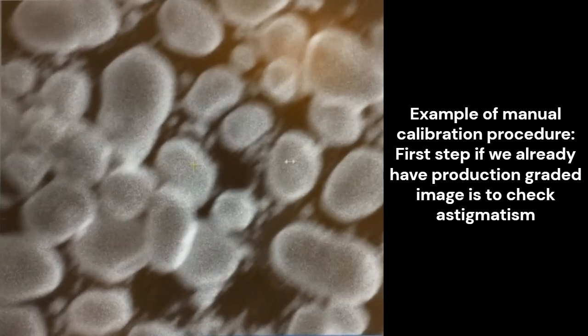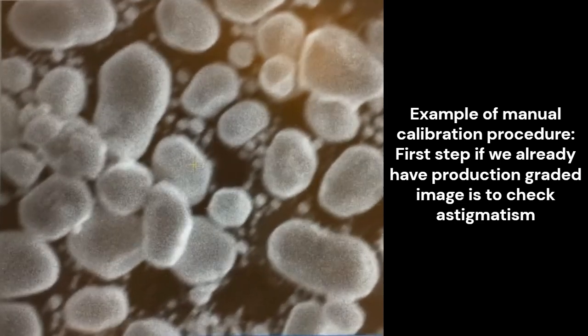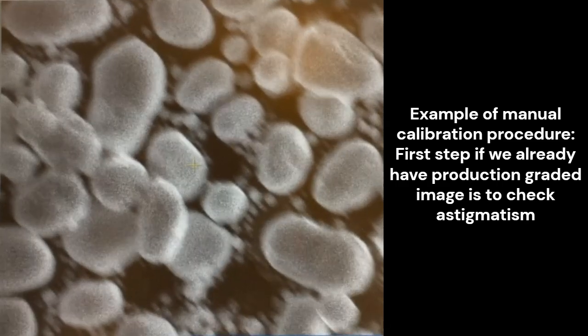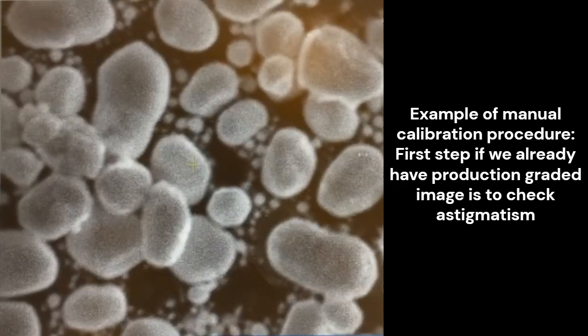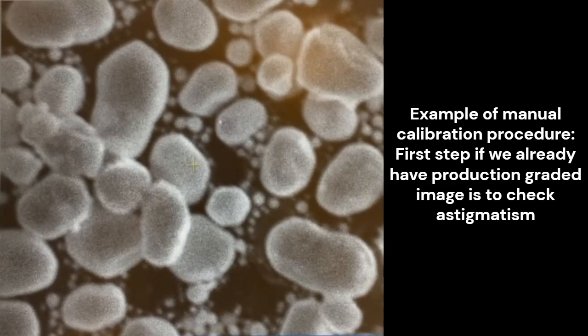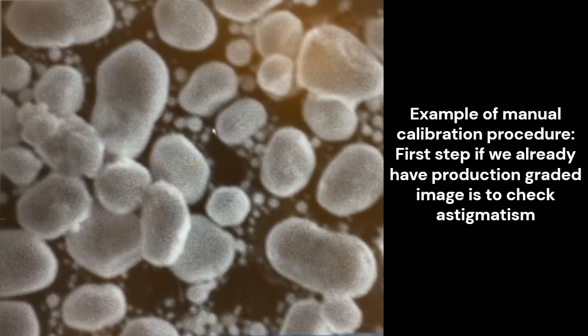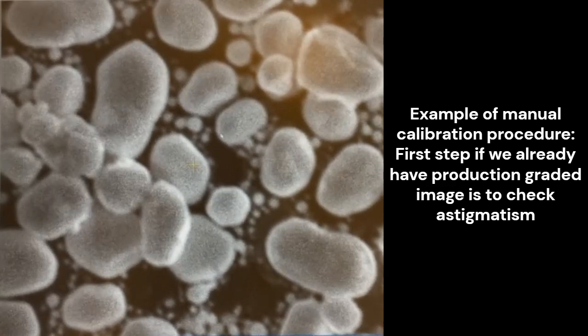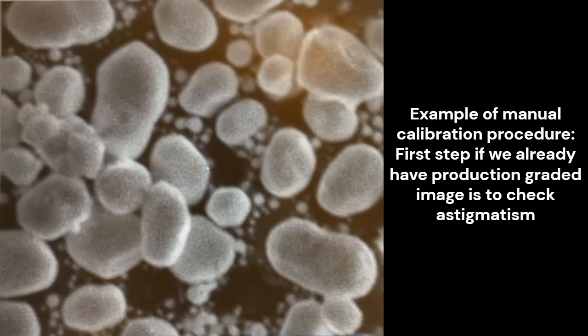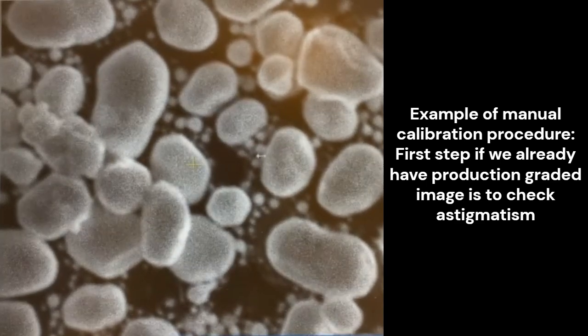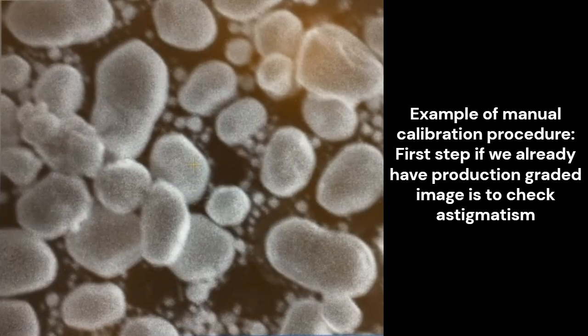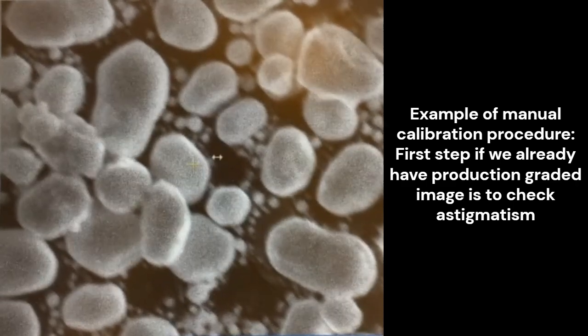So again, stretched along one diagonal, I go to the left and it's stretched on the other diagonal. I want to settle somewhere in the middle where there's no directional stretching, and instead we have, say, equal blurriness along all edges of any of these particles. So that's good focus, and again I can oscillate to the left and right and see how it stretches.